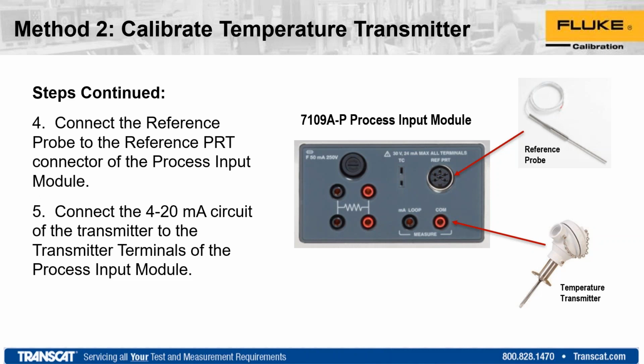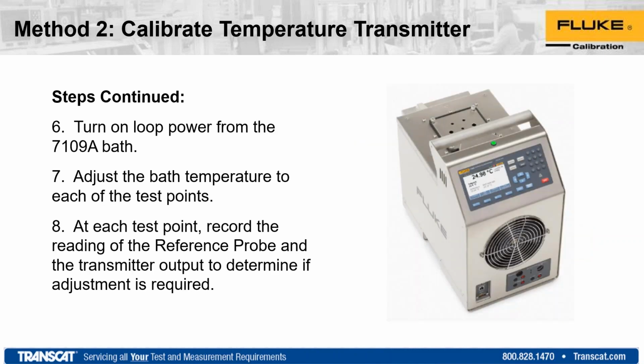There's a few connection points in there, and you would connect to the 2 outputs for the circuit. Again, pretty basic there if you've done this. When you open up those transmitter heads, there's usually 2 connections for the internal sensor and then the other 2 connections for the output that's going to go to the control board.